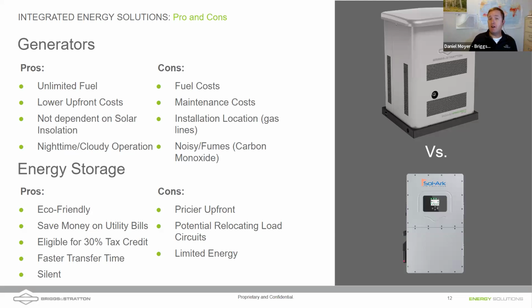One of the pros of generators is you have an unlimited fuel supply. A lot of times people have a big 500 or 1,000 gallon propane tank on the property, or they're on natural gas, which is essentially unlimited. A lot of times generators are lower upfront cost - now that's not always the case, especially if we have to run a lot of gas lines and maybe your gas meter is on the other side of the property, requiring a lot of piping and plumbing to get those gas lines over.